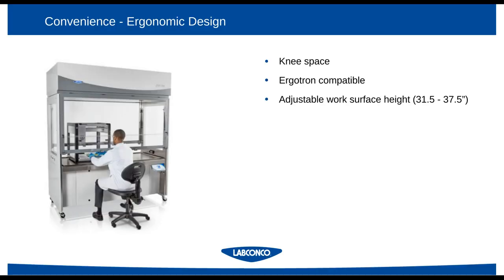Some of the other things, perhaps less pertinent to safety, but more important to comfortable use with enclosures, is ensuring proper knee space underneath the enclosure. And that means being able to reach in and safely position your body to load samples in and out of the system, and also accommodating the other pieces of equipment that go with the liquid handler or an automation system for support. So this particular Logic View includes a standard mounting system for Ergotron computer arms, which are regularly provided with automated instruments. And also the adjustable nature of the work surface is quite important.